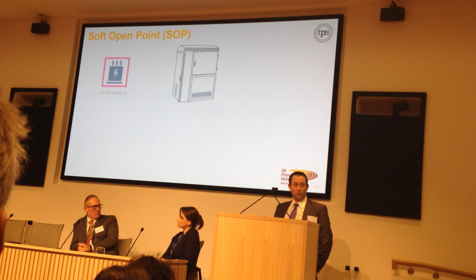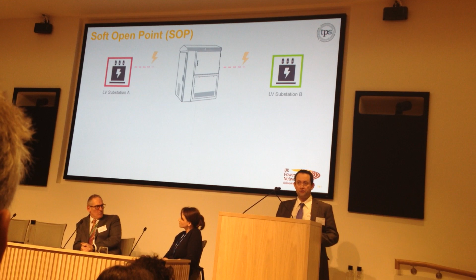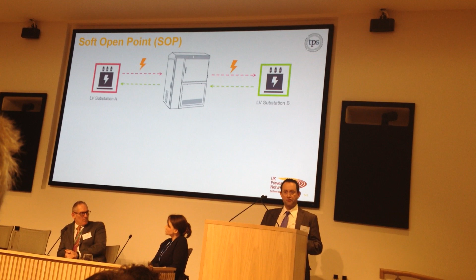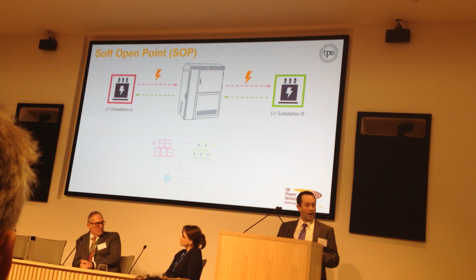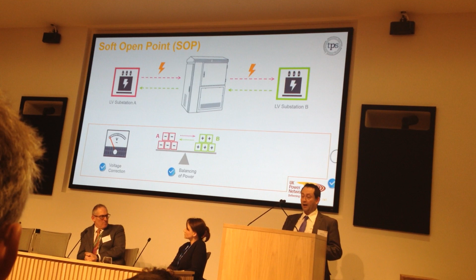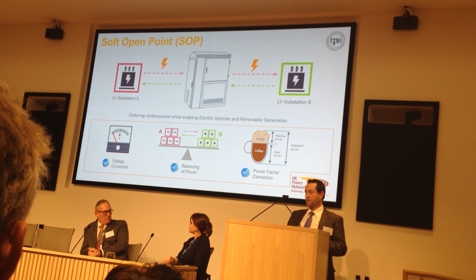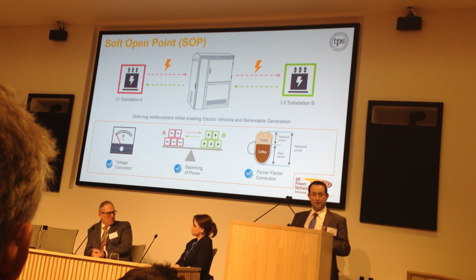I'm going to use this example, our two-terminal street furniture device. We put it into a normally open point location, and by doing so we effectively mesh two different parts of the network fed by substation A and substation B. This allows us to transfer power between substation A and substation B, and vice versa. We can also transfer power between the phases of each line, something built into the architecture of the system. Normal three-phase inverters tend to just balance on three-phase, but we can do it per phase.